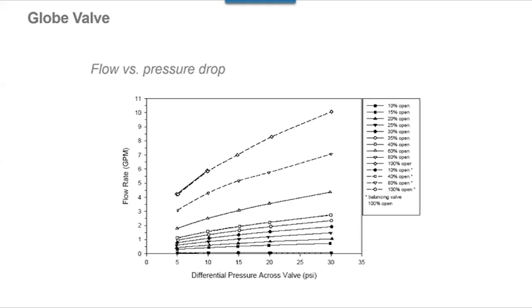In this case, this globe valve had a CV of 1.6. And as you see, here's the pressure drop across the valve. Whoops, got a little ahead of myself. Across the x-axis is the pressure drop and up the y-axis is the flow rate. So at a 5-pound drop, we're at about 1.2 GPM. Kind of consider, okay, probably the design point that you want for that valve.